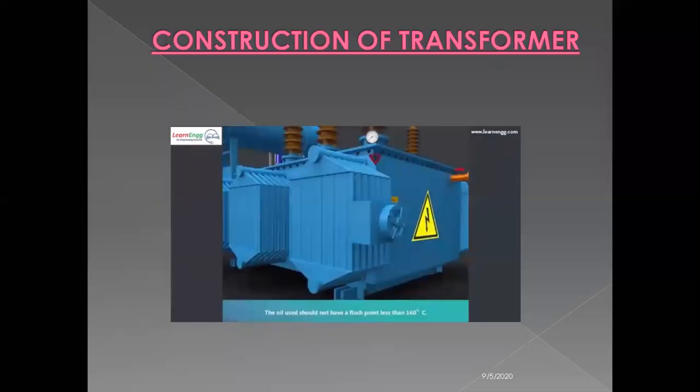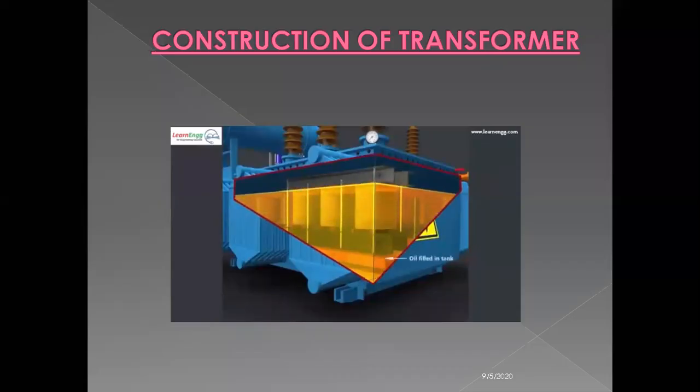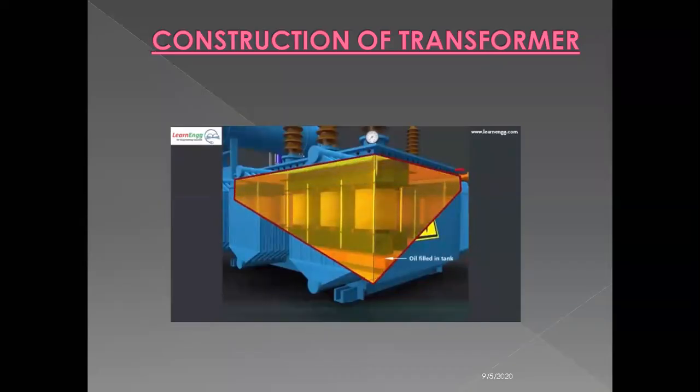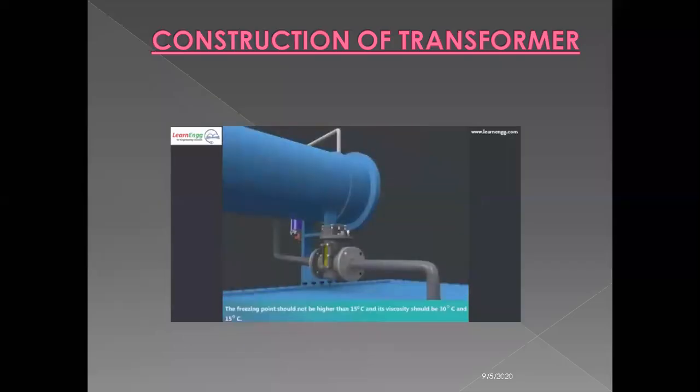The oil used should not have a flash point less than 160 degrees Celsius. Oil filled in tank: the freezing point should not be higher than 15 degrees Celsius and its viscosity should be specified at 30 degrees Celsius and 15 degrees Celsius.